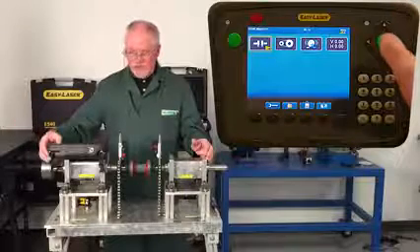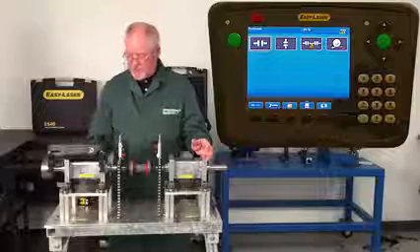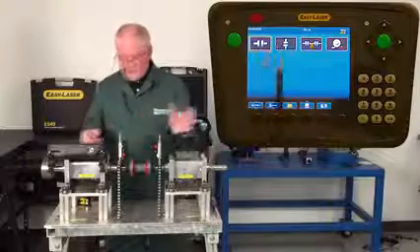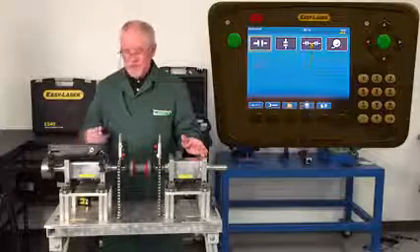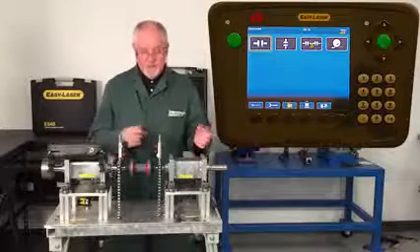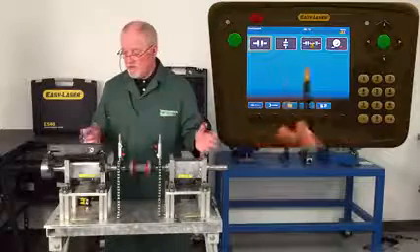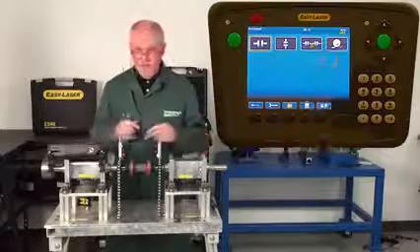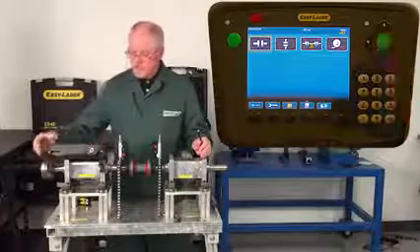Today we're going to focus on the shaft alignment, the simplest. So here's our shaft alignment programs, and as you can see, we've got shaft alignment horizontal, we've got shaft alignment vertical, we've got multi-train units. So say a motor that's driving a gearbox, that's driving a pump, and we can do that. And we also have a soft foot program. Okay, right now we're just going to go and do horizontal alignment, so I choose that.